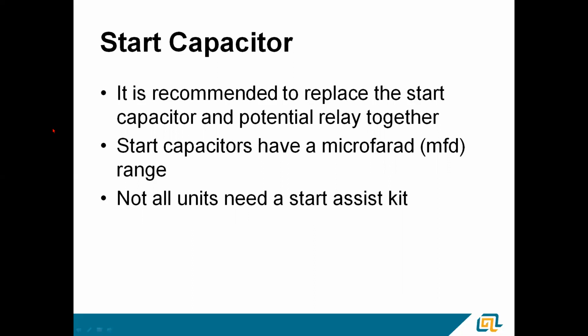Again, the capacitors have a microfarad range, not just a set microfarad. And not all units will have a starter kit, assist kit. It's something that you might find that you need in certain conditions. With the advent of scroll compressors, it's less and less likely to be needed, but they are available for all our kits. And there's a lot of aftermarket kits. I always carried Super Boost, the SPP5, SPP6, something like that. Always had one of those on my truck for that compressor that just wouldn't start.